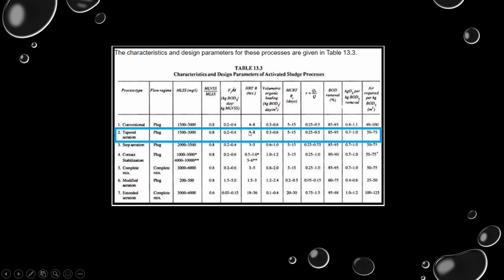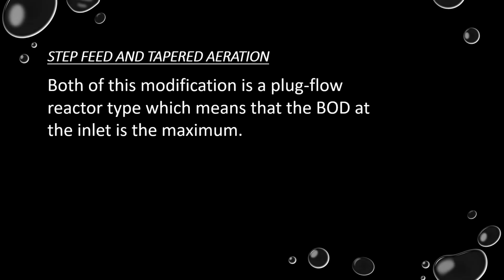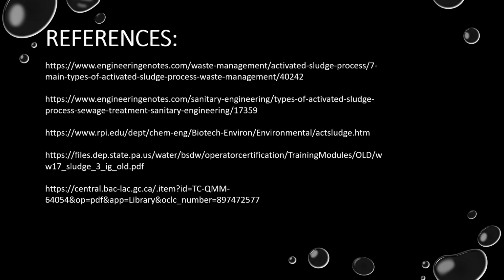And the detention time of tapered aeration is 4 to 8 hours. And the BOD removal is still 85 to 95%. Okay, so step feed and tapered aeration, both of these modifications are plug flow reactor type, which means that the BOD at the inlet is the maximum.